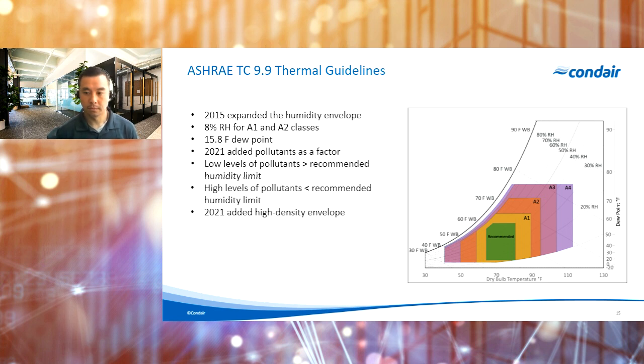The recommended temperature and humidity ranges are ideally where IT equipment operates the majority of the time, though a number of allowable ranges have been added that allow the envelopes to expand beyond the recommended range. It's generally acceptable for IT equipment to operate in these allowable ranges for limited amounts of time with negligible effects to reliability. As the temperature and humidity ranges have grown, it's really presented an opportunity to greatly reduce requirements for mechanical cooling. In the last decade or two, many facilities have been designed to leverage economization even 100% of the time and completely eliminate the need for mechanical cooling and air humidification.